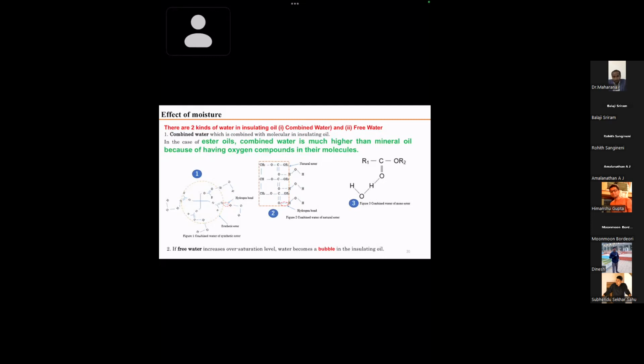During pouring, some conclusions say that since ester fluid has more water holding capacity, it increases the lifetime of paper or solid insulation inside transformers. The idea is that if there is moisture in the oil, not so much water will be accepted by the paper, creating a balance. I have studied this paper, but I don't completely agree with the statement that higher moisture holding capacity in the oil increases lifespan. From my research perspective, I don't think this is correct. As I said from the beginning, it's a controversial statement, since we haven't concluded the certain physics behind it. But still, avoiding moisture will be better for both insulation systems.